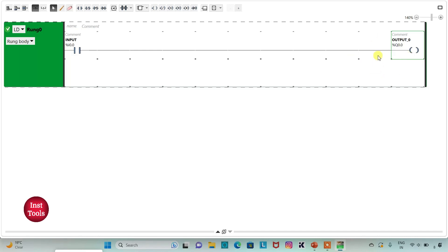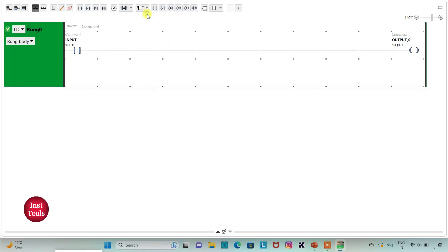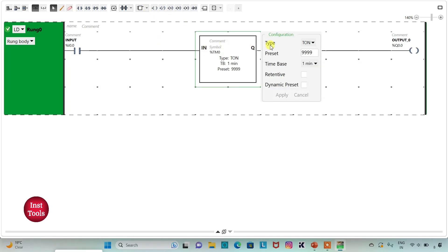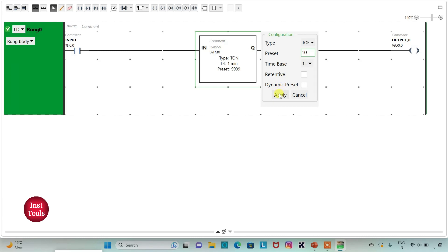To keep the output on for some time even when the input is turned off, we will use a timer here — that will be TOF. I will change the time base to 1 second and the preset value to 10, for example, then click Apply.